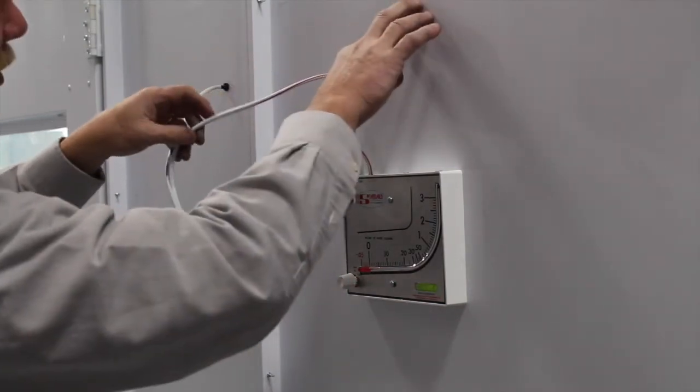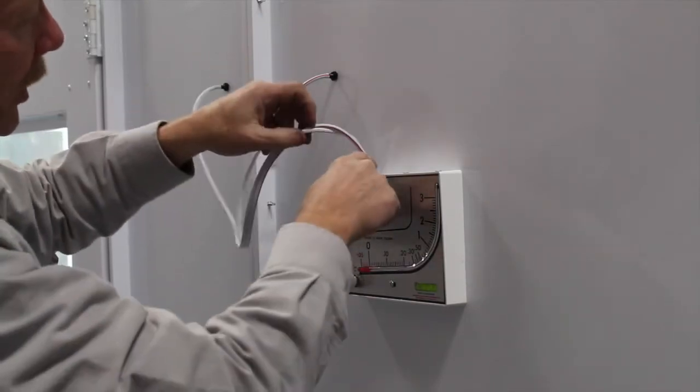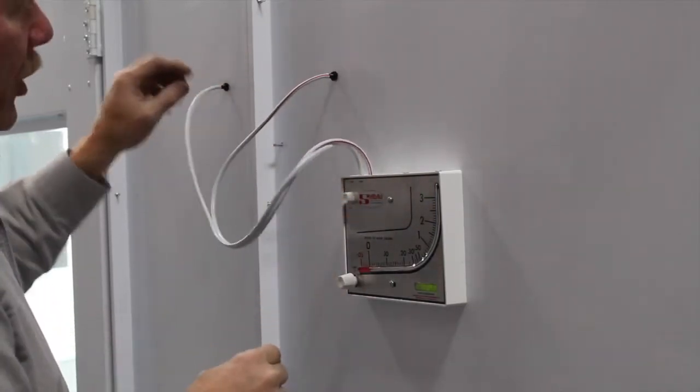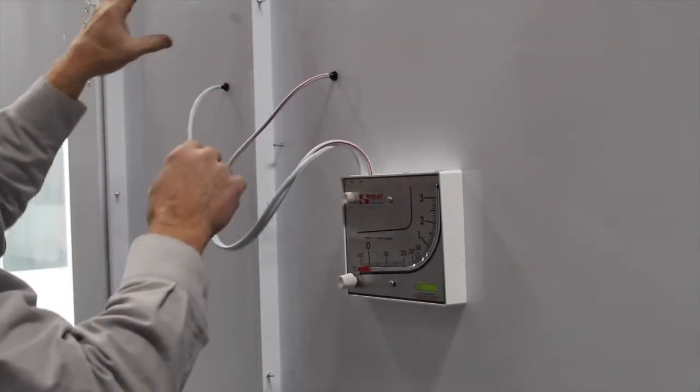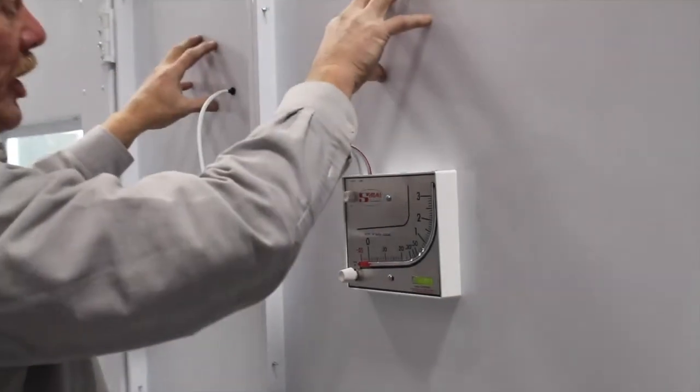This is low pressure. The red to low. And the high pressure is not marked so it goes to high. So the filters are here. We are reading the differential pressure between here and here.